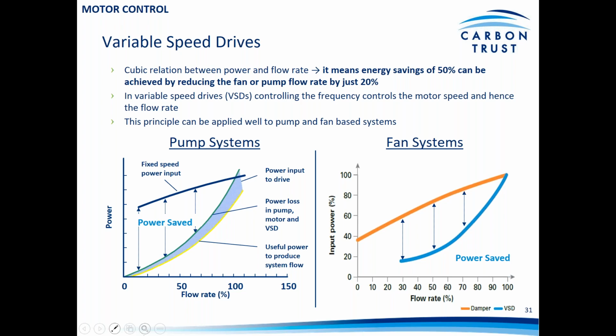So that's where the big savings come in, and it makes a significant difference for variable torque loads if you can apply a variable speed drive. That applies to the pump systems, as we see here, also to fan systems. You can see in the chart on the right that there's the same principle in terms of the level of saving and the profile of the graph. So anything that has a variation in flow rate, you can apply variable speed drives to quite effectively.